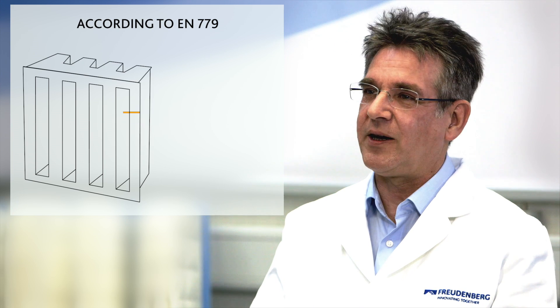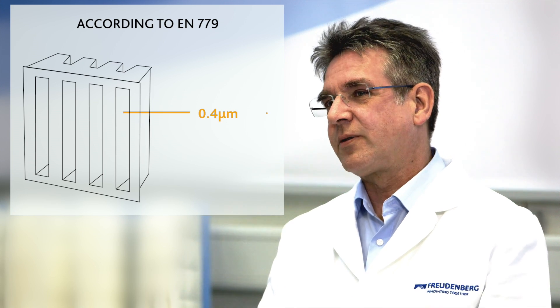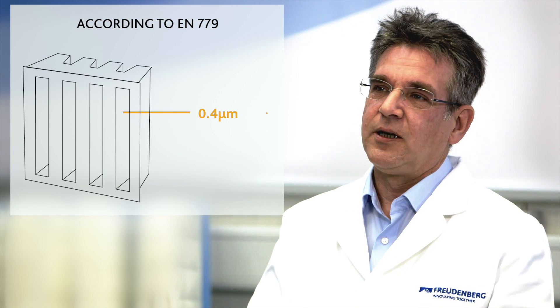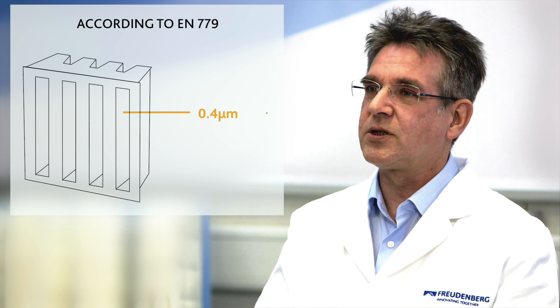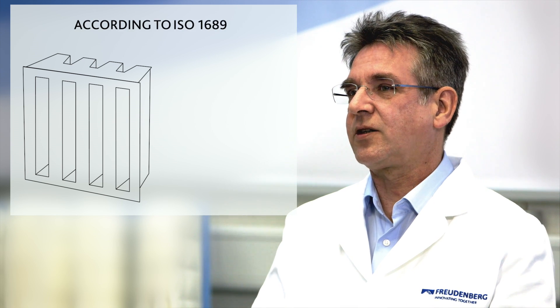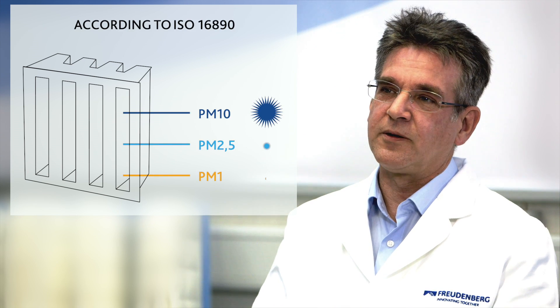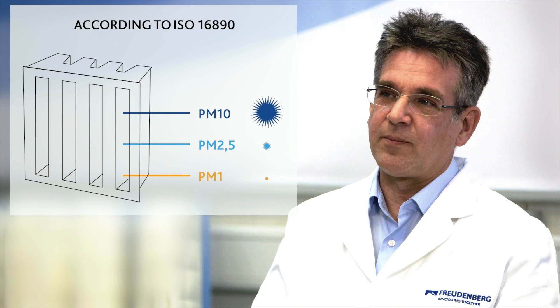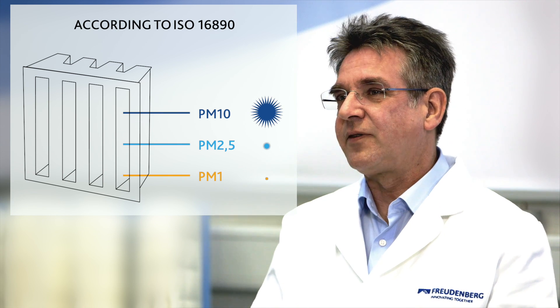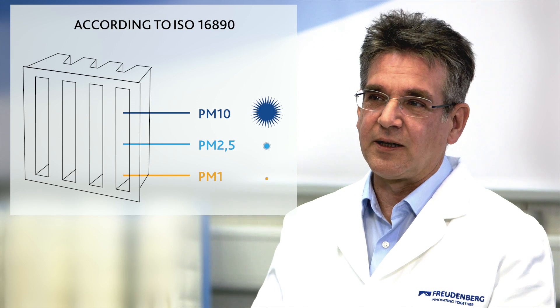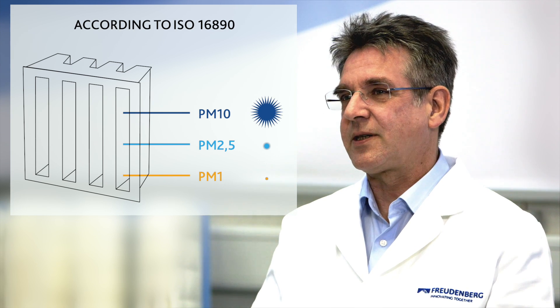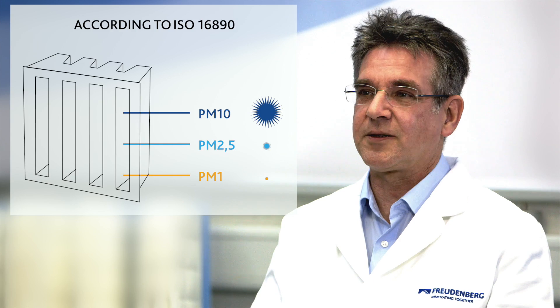Furthermore, the new standard considers the entire particle size range from 0.3 to 10 micrometers, which will enable us to evaluate a filter's efficiency for the fine dust fractions PM10, PM2.5, and PM1. For example, we will rate a filter in the future as an ISO EPM10 80% filter, which means it removes 80% of the PM10 fine dust fraction.